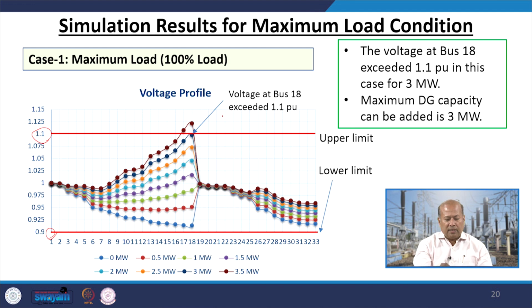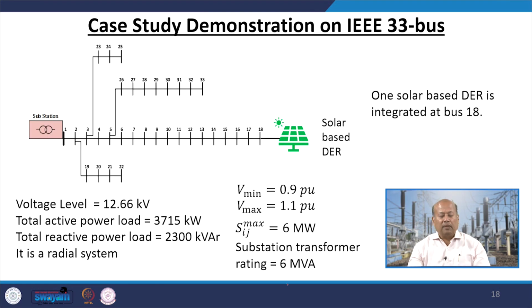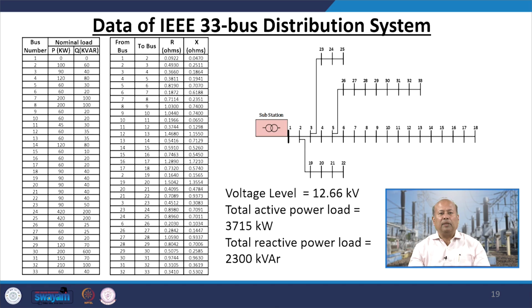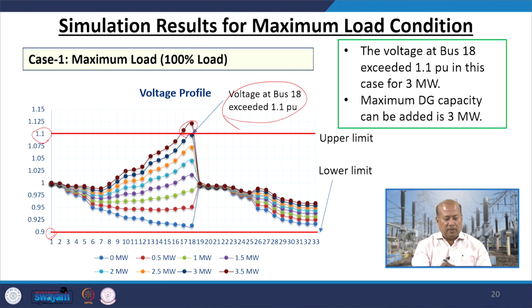But voltage at bus number 18 is exceeding 1.1 per unit. Why is it happening? All of you please have a look here. So, at this bus number 18, now we are injecting extra power through PV. So, when you are injecting extra power through PV, that means the voltage experienced at bus number 18, as you could see, is slightly high now. So, the voltage at bus 18 exceeds 1.1 per unit in this case for 3 megawatt of penetration.